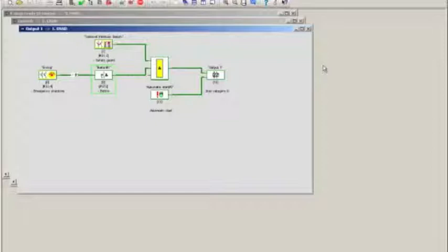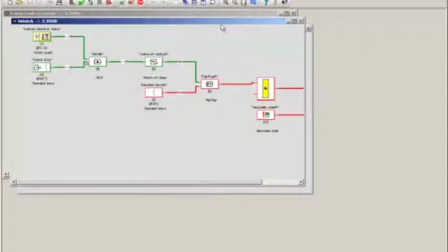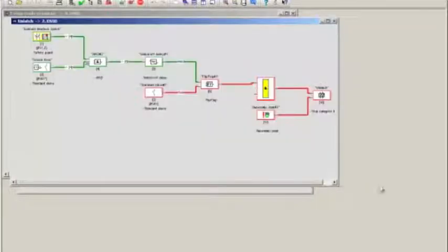Recall please that the signaling, the messaging outputs are not going to be strong enough to provide the necessary current. Those are per data sheet 10 milliamps of current. They're good for LEDs, they're good for inputs into PLCs, this kind of thing. But they're not going to be strong enough to unlatch, to pull in the solenoid on this door switch. So therefore, I am utilizing OSSD2 as my means of turning on the solenoid. So I use the safe output 2 that's on the controller to do that.